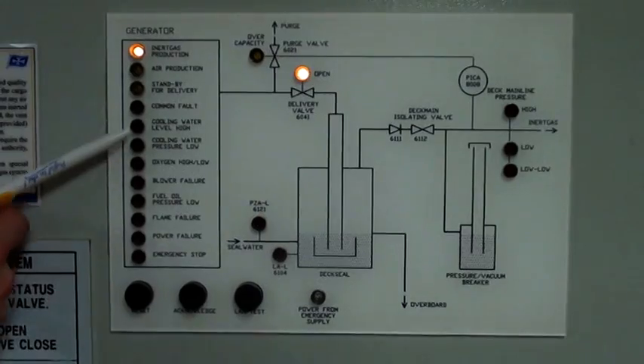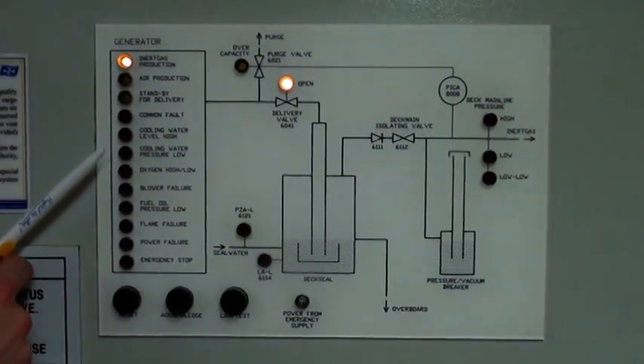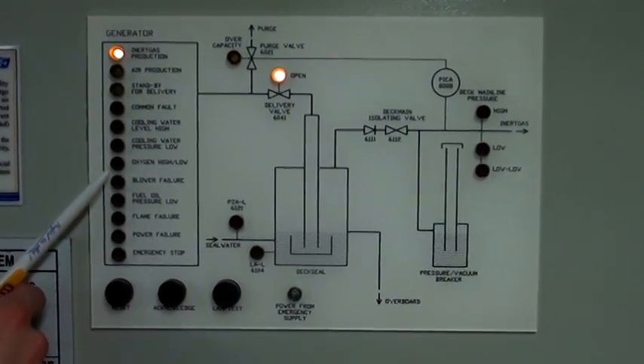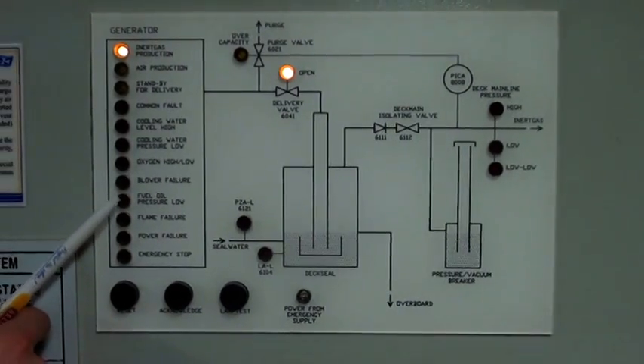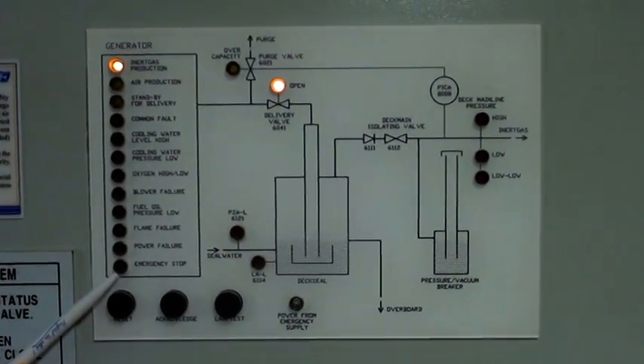The red indications are for alarms like common fault, cooling water level high, cooling water pressure low, oxygen high/low, blower failure, fuel oil pressure low, flame failure, power failure, and emergency stops.